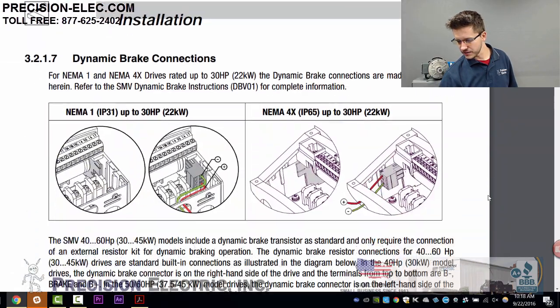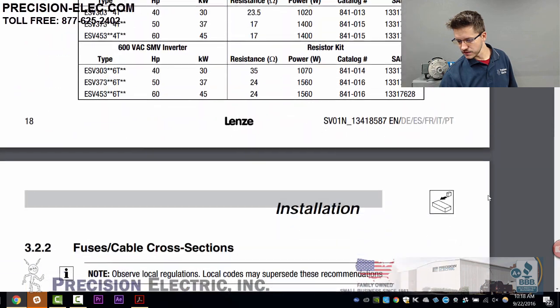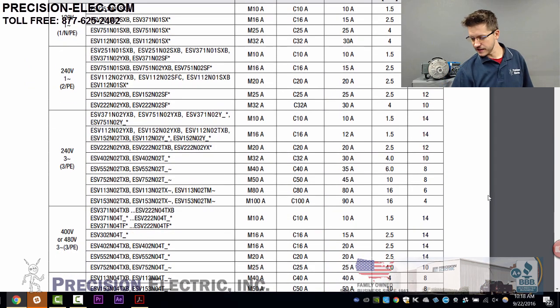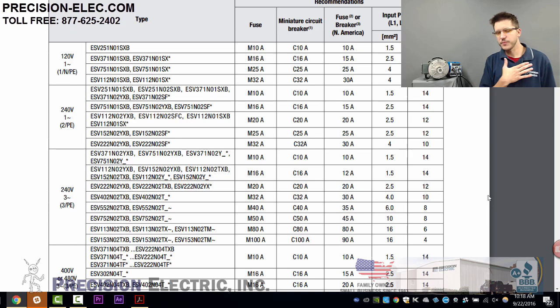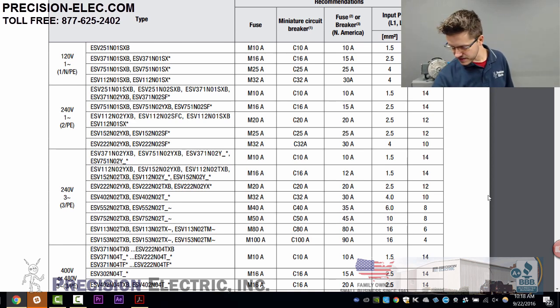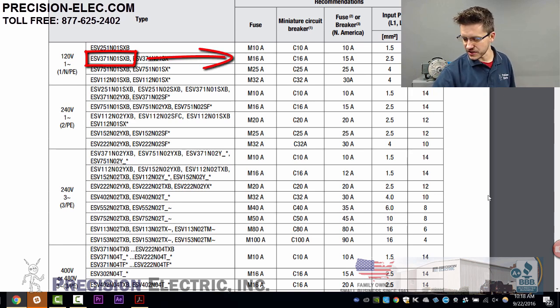Let me scroll all the way down to the fusing chart. The fusing chart in the manual is organized by part number. My drive's part number is ESV371N01SXB. I look that up in the chart and follow it across to the right — it says I can use a 16-amp fuse, a 16-amp breaker, or a 15-amp fuse. It even gives a recommended part number for the fuse and recommends 14 gauge wire.